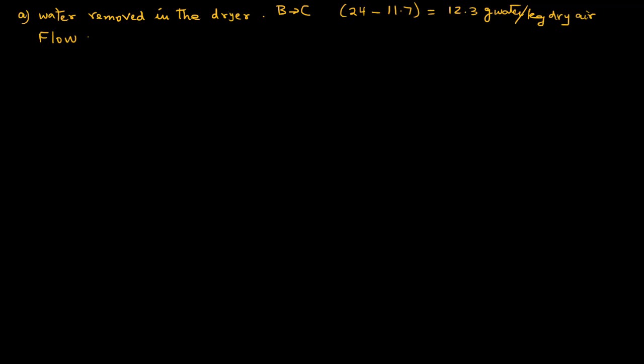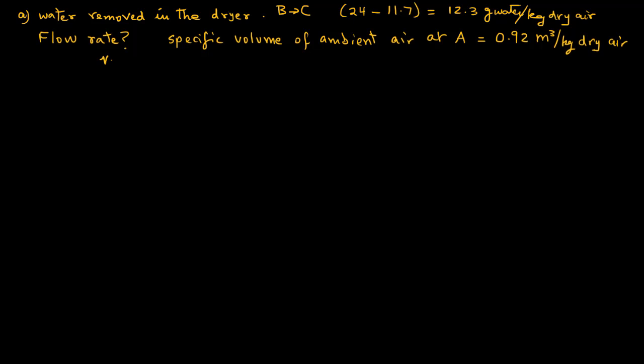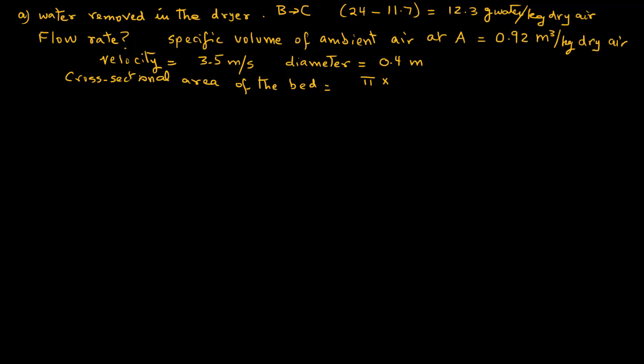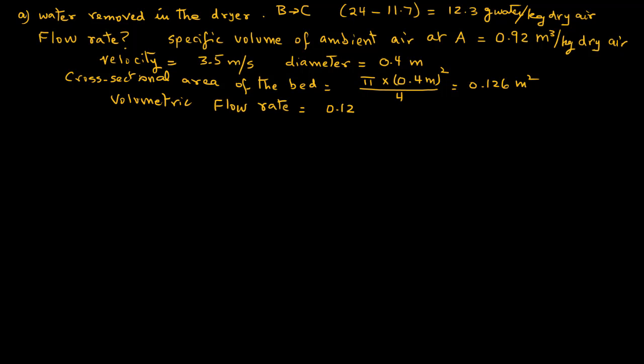Now we want to determine the mass flow rate. From the psychrometric chart we have the specific volume of ambient air at A as 0.92 cubic meters per kilogram dry air. The velocity of the air is 3.5 meters per second and the diameter of the bed is 0.4 meters. The cross-sectional area of the bed will be π d² / 4, or π × (0.4)² / 4, which equals 0.126 square meters. The volumetric flow rate will be the velocity multiplied by the cross-sectional area: 0.126 × 3.5 = 0.44 cubic meters per second.